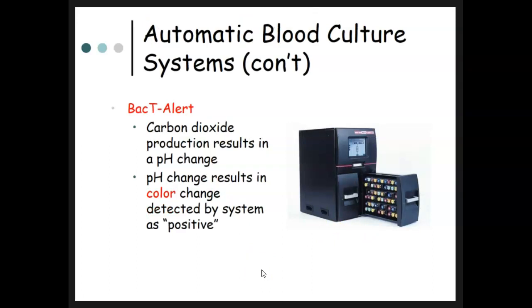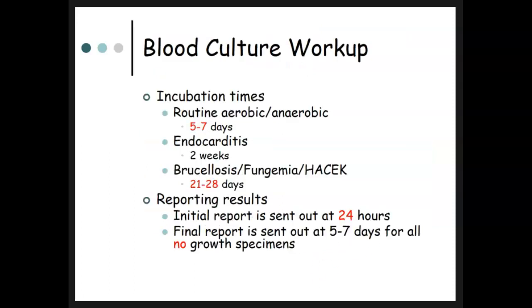BactAlert is a carbon dioxide production change, so it results in a pH change. And the pH change results in a color change, which is detected by the system as positive. So again, there's a light in here that detects the color change, and then an alarm will sound.